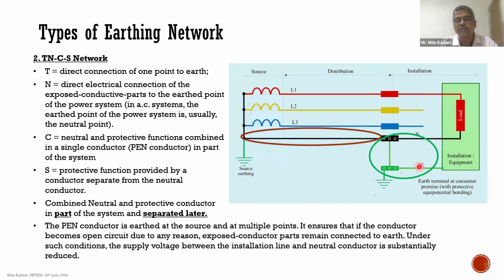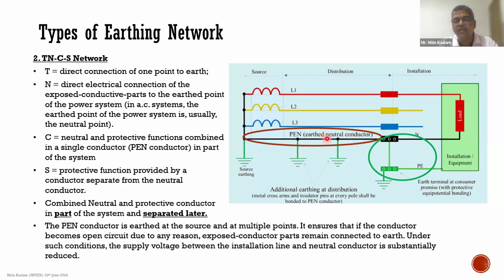Okay, so this is the difference. If you say TNCS, it is a combined neutral and earth coming up to a certain point, and further on it gets separated, and therefore it is TNCS. Now, this PEN conductor is also earthed at multiple locations. So in case of breakage of this PEN conductor, it is possible to limit the voltage on the neutral, so no shock hazards are exhibited.